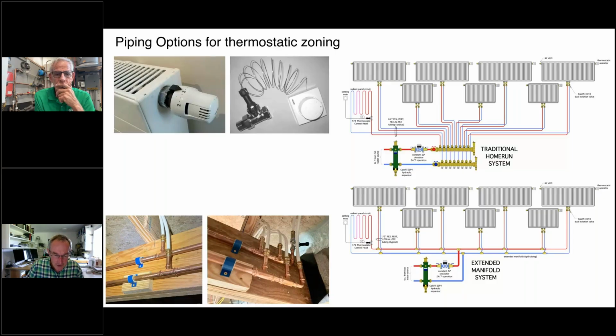Here's actually an example of the capillary tube. If you look really close in that photo, you could probably see that little, what looks to be a wire. And that goes off to a radiant floor circuit. These two go off the panel radiators. So as long as your panel radiators and your radiant panel circuits are basically sized for about the same water temperature, it's fine to combine these on the same system.